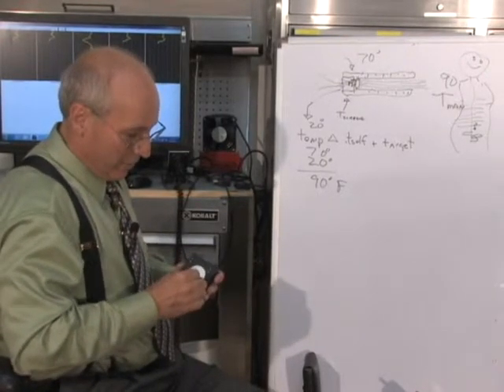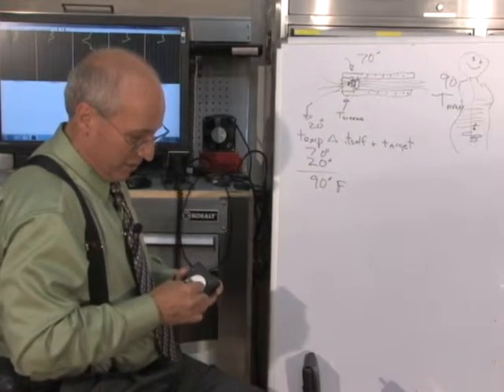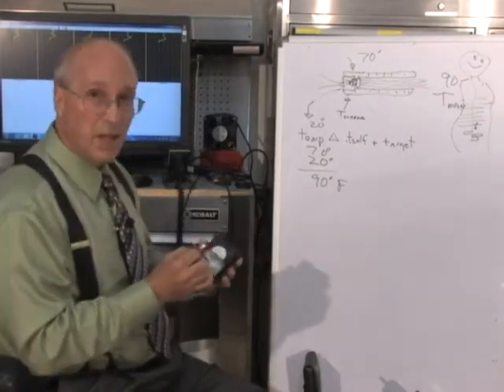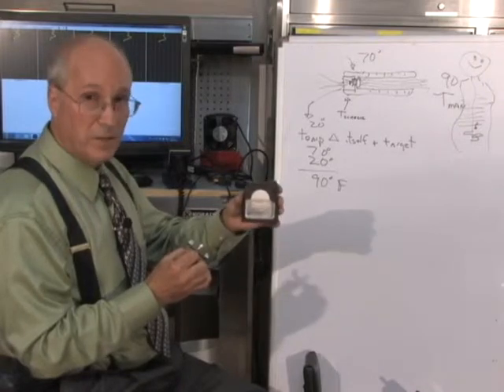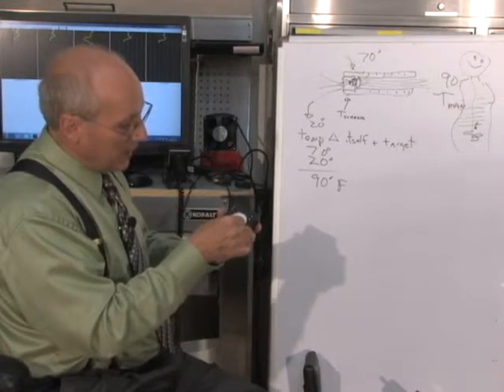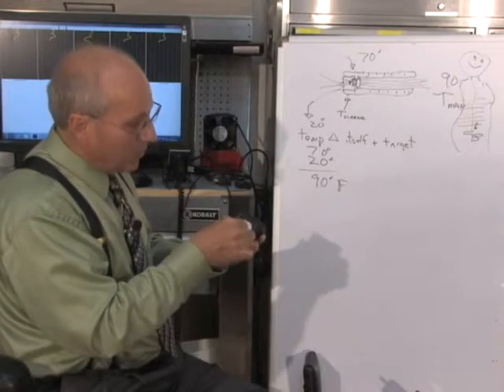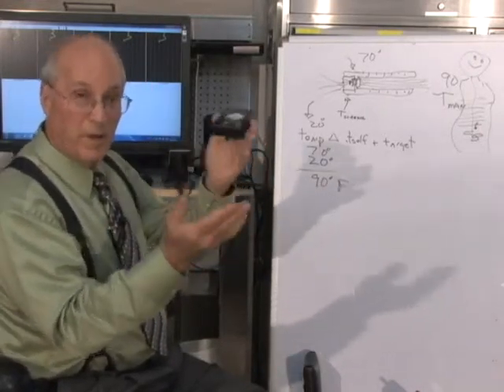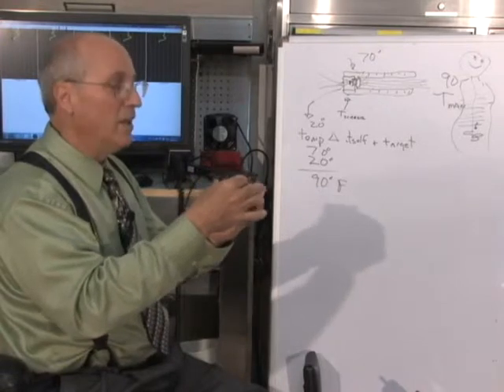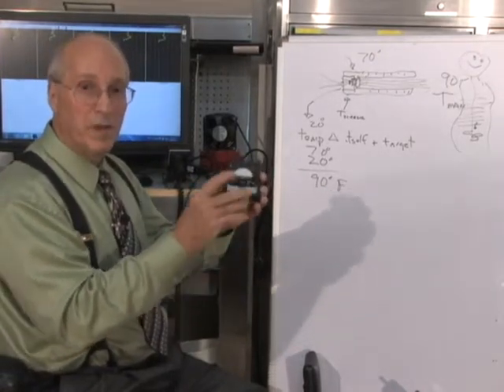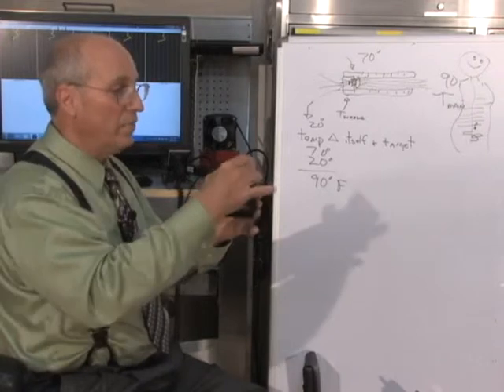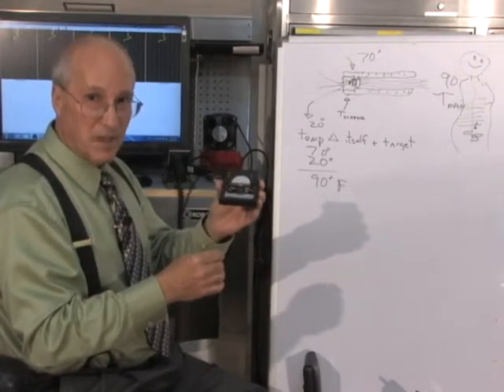One of the things that I wanted to share again in the design of a scanner and why our scanner only has two barrels—in order to maintain that balance on the head of the scanner, the circuitry that is within the scanner must be laid out. The circuit board itself must be laid out equally, placing amplifiers on both sides equal distance from the center. So any small amount of heat that the electronics generates is generated equally on both sides within the head. You can't have three or five or any number other than two barrels on a device and expect it to be stable and remain stable.